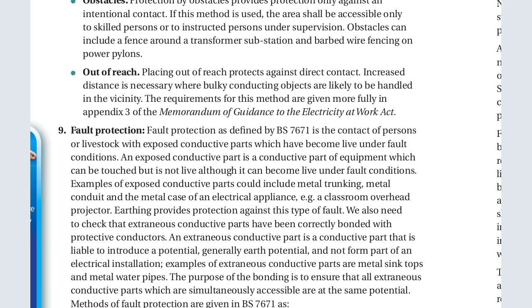So sometimes we have conductive parts that were sealed or concealed, but they have become exposed under fault condition. So an exposed conductive part is a conductive part or equipment which can be touched but is not live, although it can become live under the fault condition. Examples of exposed conductive parts could include metal trunking, metal conduit, and the metal case of an electrical appliance, e.g. a classroom overhead projector. Earthing provides protection against this type of fault.